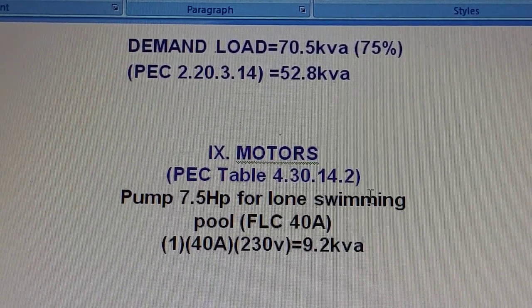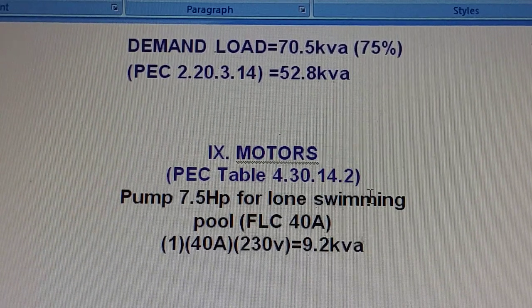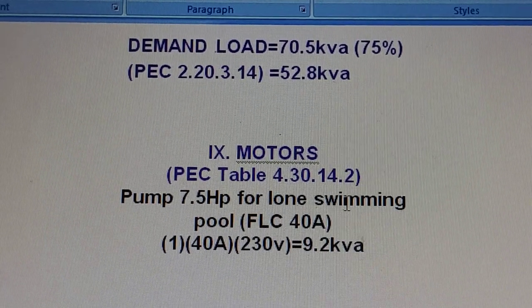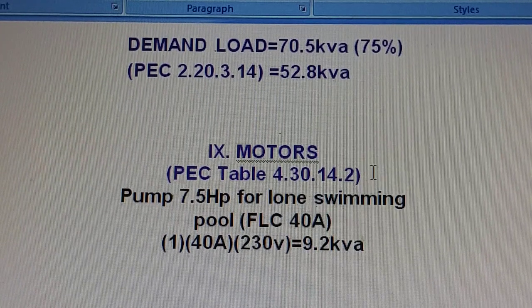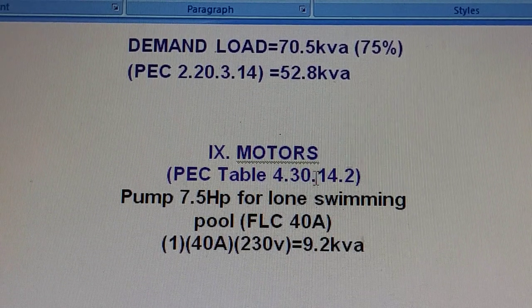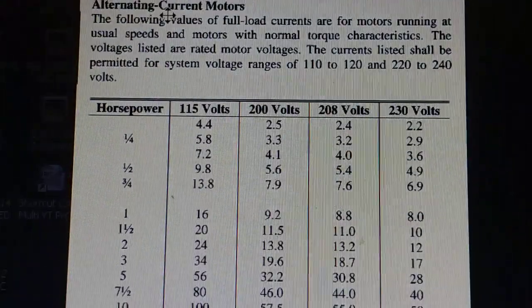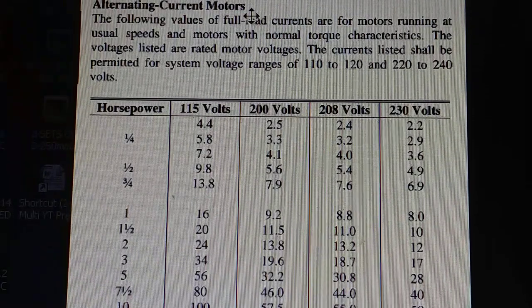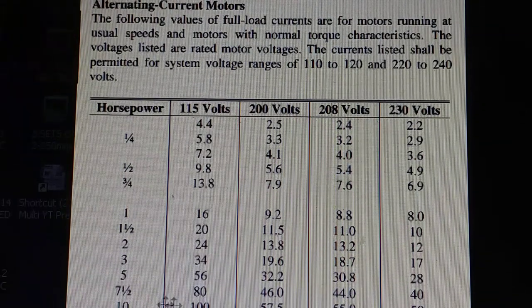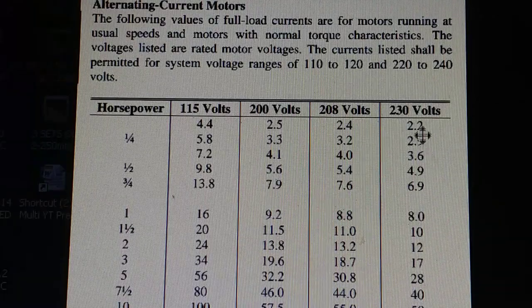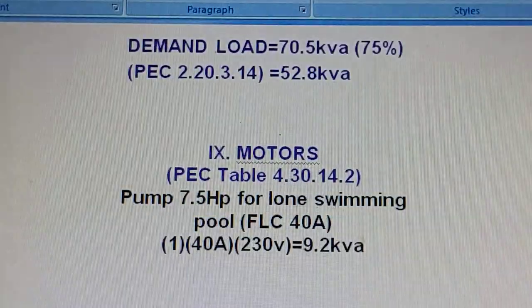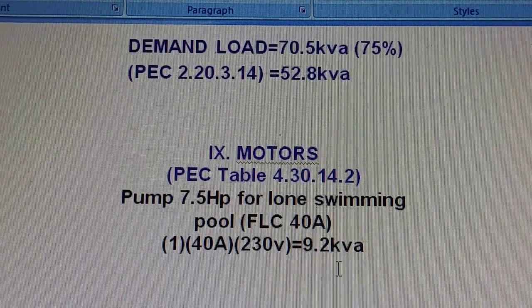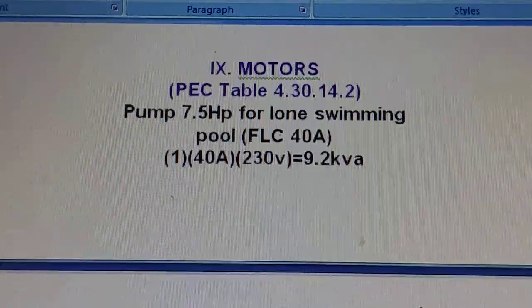For motors, we have only one induction motor here — the pump motor for the swimming pool — with an FLA of 40 amps. We don't have the nameplate, but the HP is 7.5 HP. We go to Table 4.30.14.2 for the full load current for single-phase alternating current motors. For 7.5 horsepower at 230 volts, we get 40 amps. So 40 amps times 230 volts gives us 9.2 kVA for the motors.